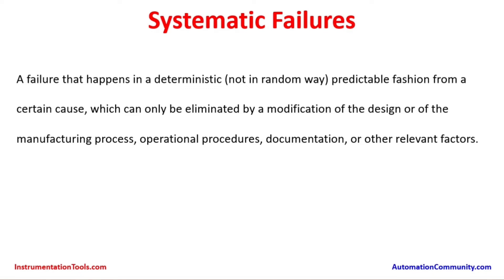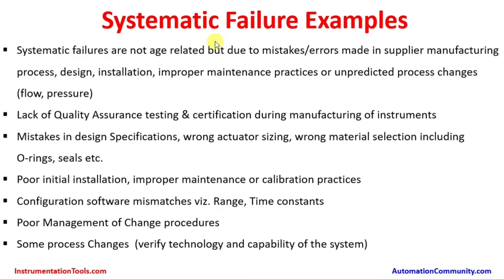Systematic failures are not age-related but due to mistakes and errors made in supplier manufacturing processes, design, installation, improper maintenance practices, or unpredicted process changes in flow and pressure. If the process operation is changed to achieve higher production output or throughput, the flow or pressure in the piping can exceed design limits at certain times, creating chances of failure.